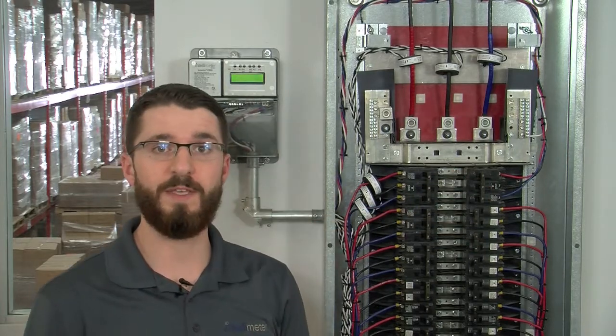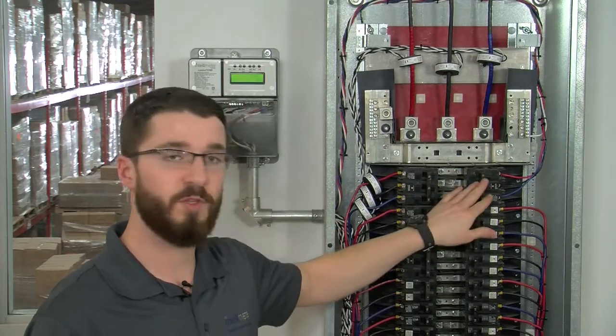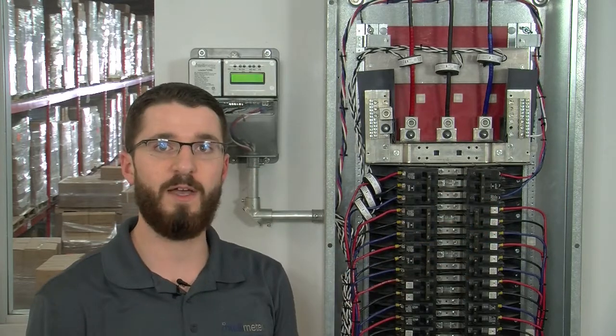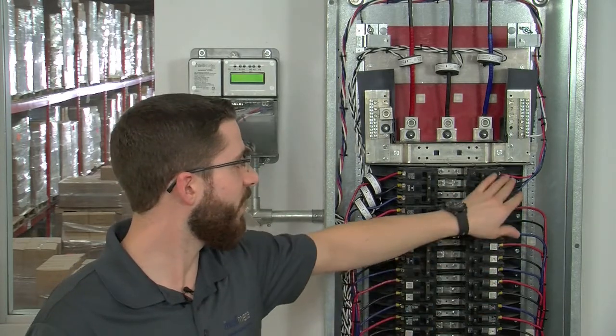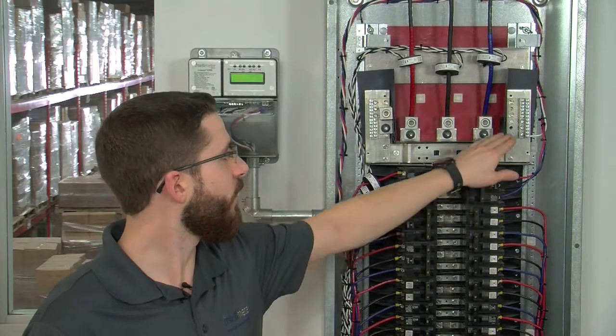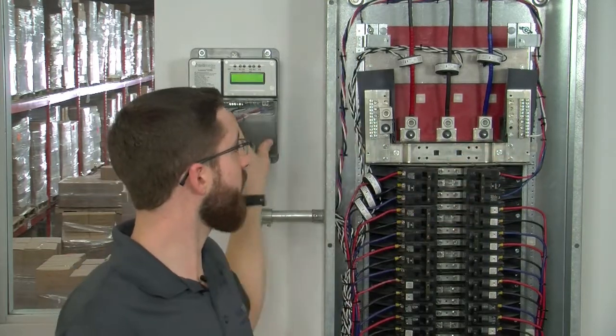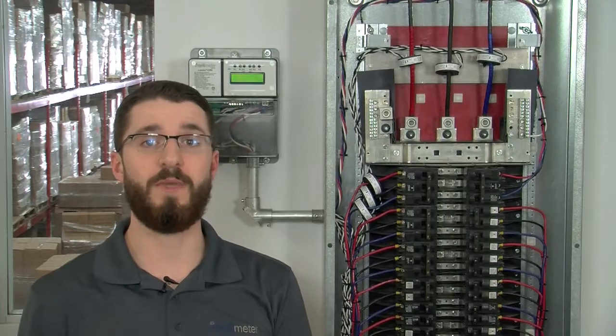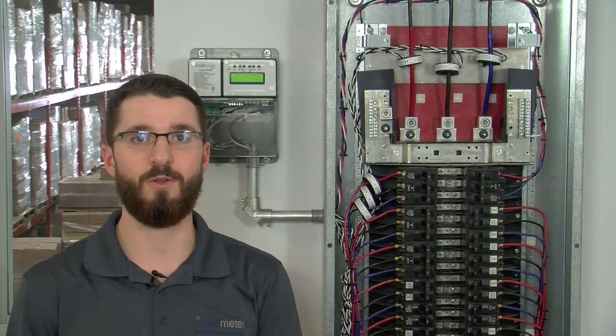We're going to want to repeat the phase test that we just covered for the breaker intended for the reference voltage, and once the phasing is identified, we can go ahead and terminate one end of the wires into the breaker and neutral block and run the 4 wires back to the meter enclosure. You're going to want to make sure to use colored wires specific to your local electrical code.